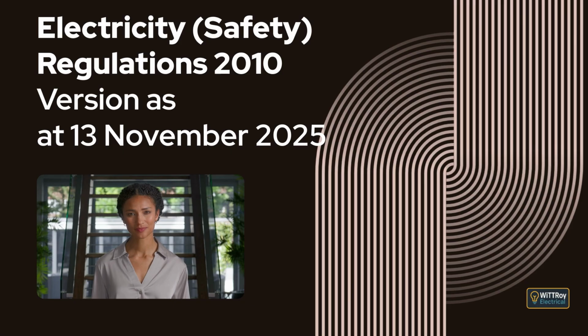Reg 74 Electrical Safety Certification. This regulation explains that it applies to prescribed electrical work carried out on an installation, a part installation, or any fitting that supplies electricity to an installation or part installation. It explains that once the work is complete, the person who completed it must issue an electrical safety certificate if they are satisfied that the installation or part installation is safe to use, is electrically safe, complies with the regulations, and that any maintenance, alteration, or addition has not adversely affected other parts of the installation.